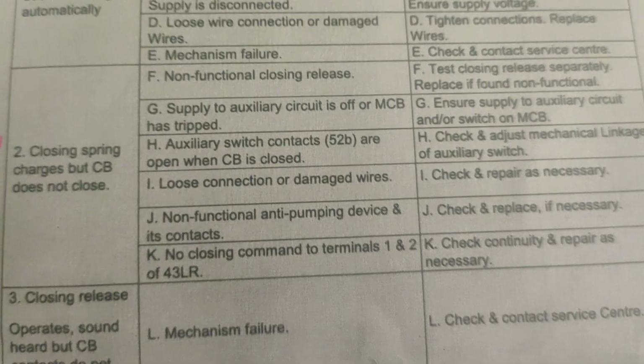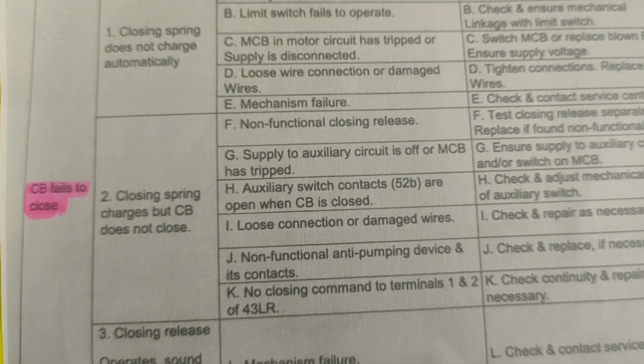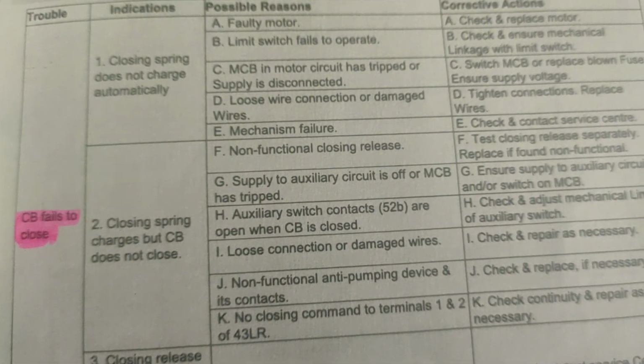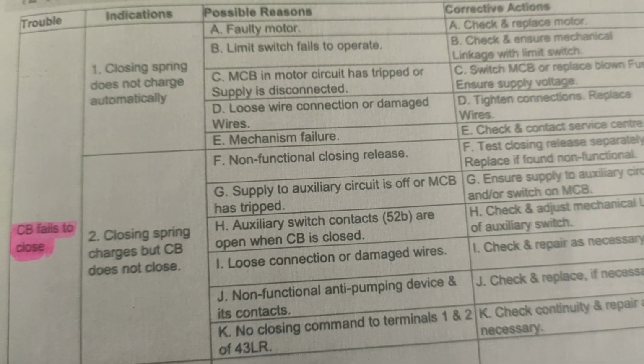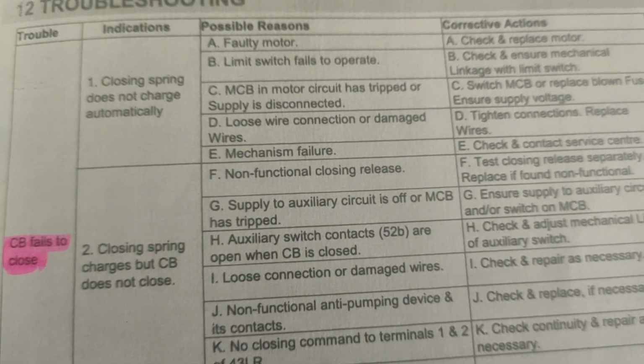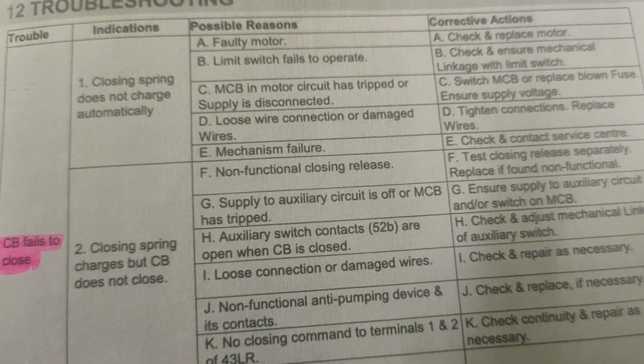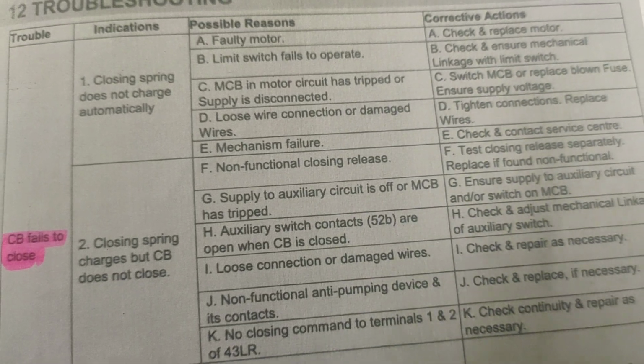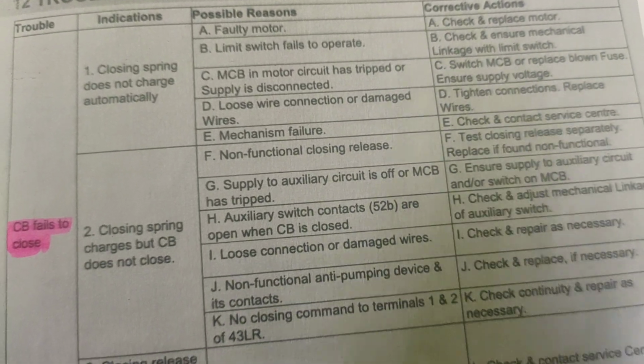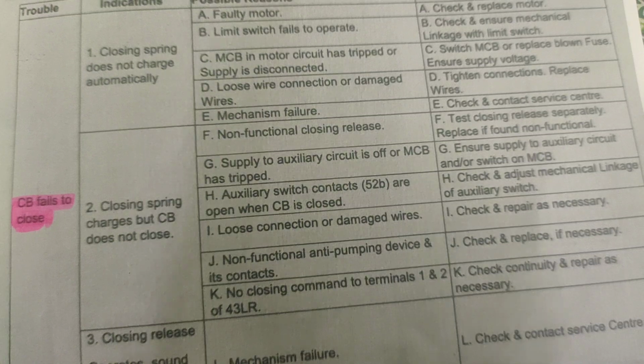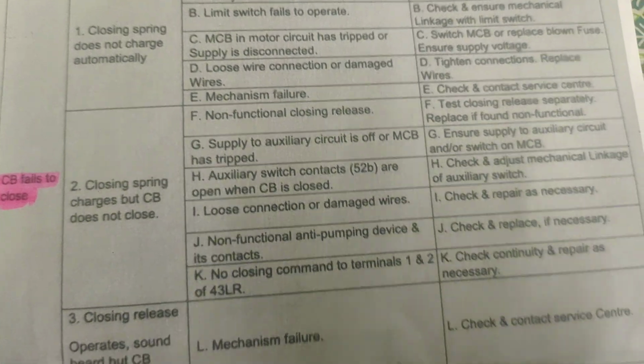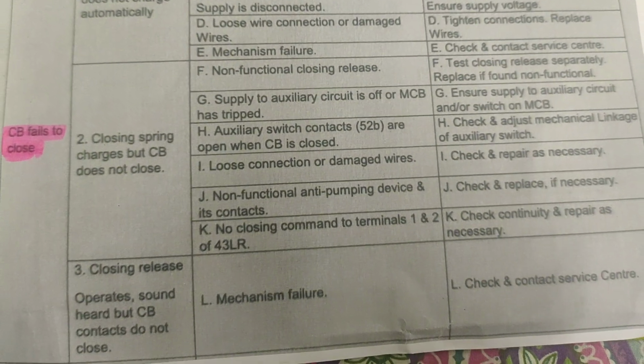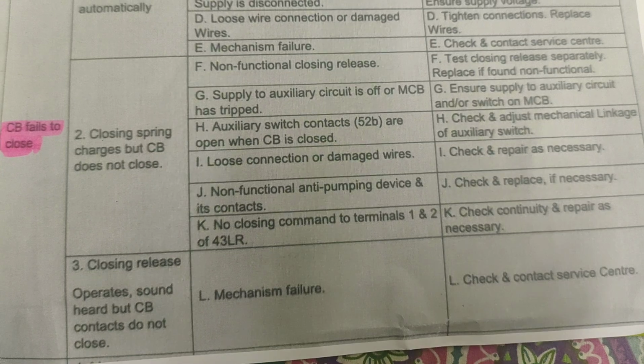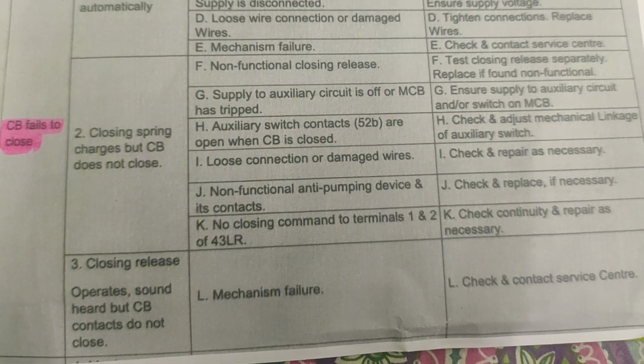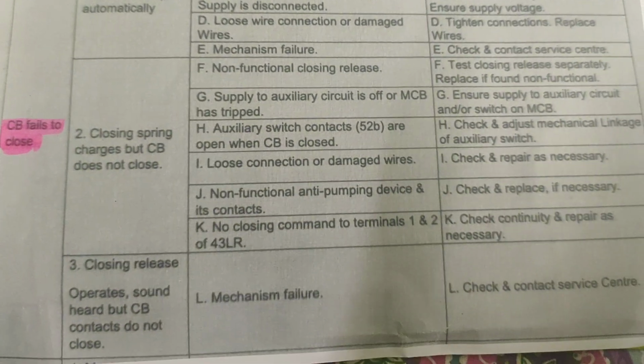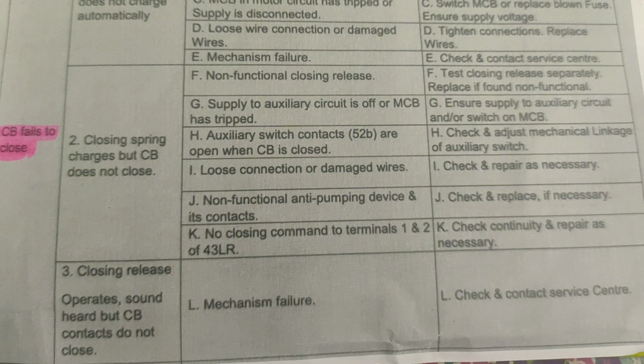So if these types of problem are there, the circuit breaker cannot be closed. So what will be the problem? Closing spring. The first problem is the closing spring does not charge automatically. You have to remember, closing spring charges but circuit breaker does not close. And closing release operates, sound heard, but circuit breaker contact does not close. So these types of problem may be there.